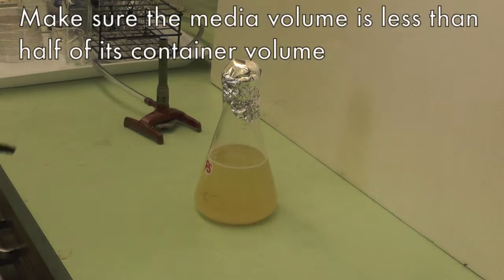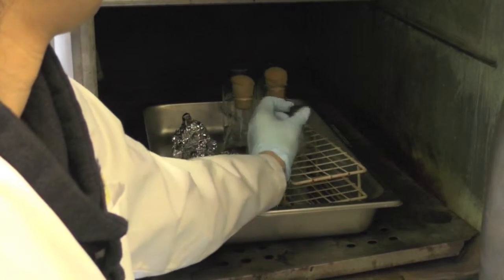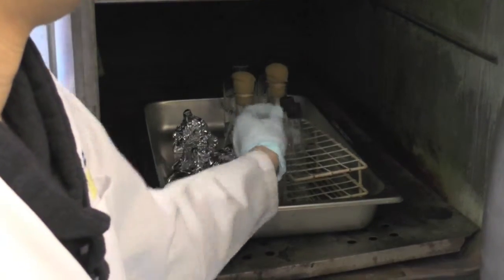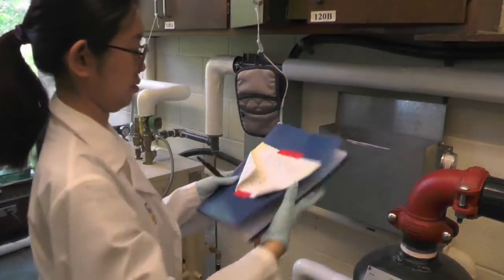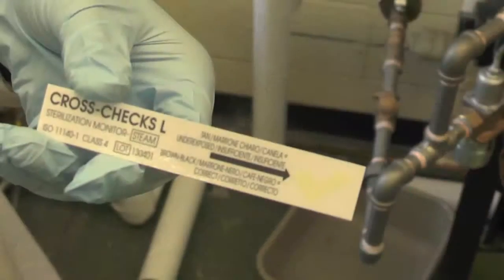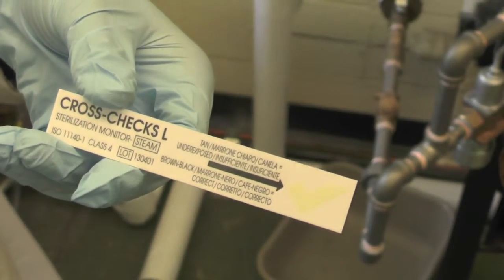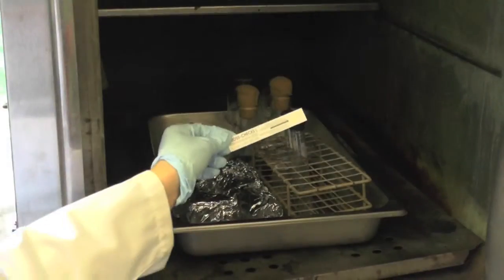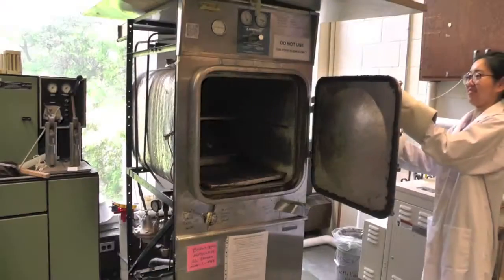If you are to autoclave media, please ensure the volume is less than half of the container volume to avoid spillage. All bottles and screw cap tubes must be loosened to avoid pressure buildup. Once all the materials have been put in the autoclave, place a chemical indicator strip with your load to ensure the autoclave has reached the sterilization temperature.